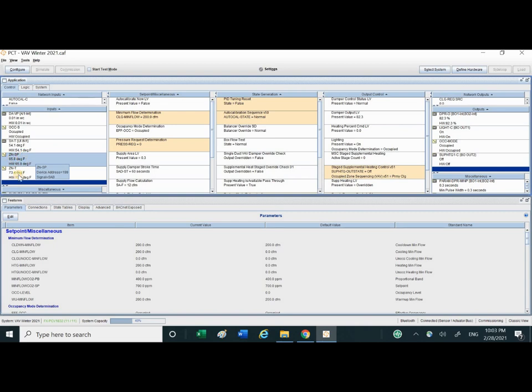If the set point is higher than zone temperature, then the heating should be on. Let's change the zone set point higher. Now it's higher, 70, 72, 73. Let's make it higher. Okay, 78.5 now. Can see now the zone set point is 78.5. Here it says 78.6 here. It's higher than zone temperature. So the output here, the heating, it's on. Now we see the off cycle.